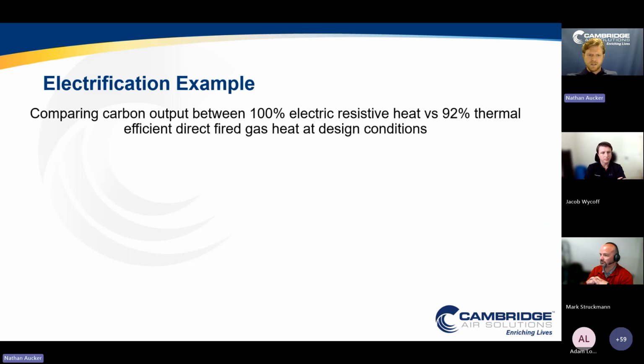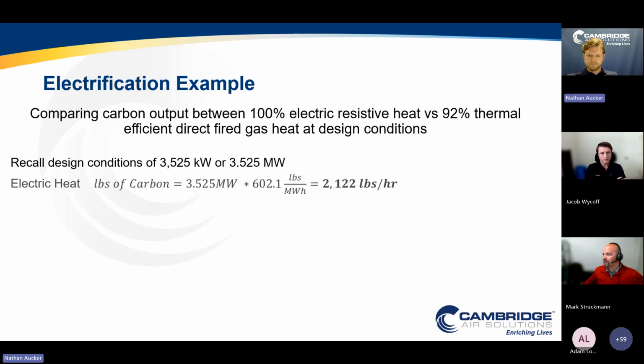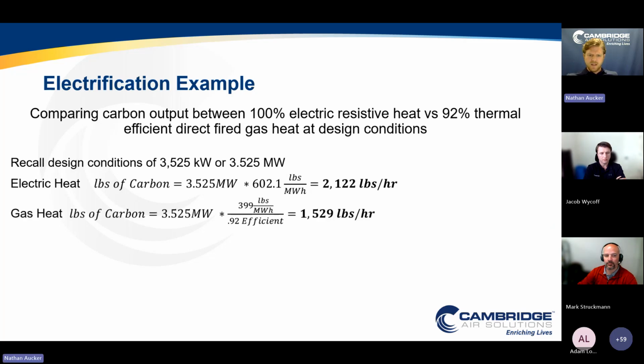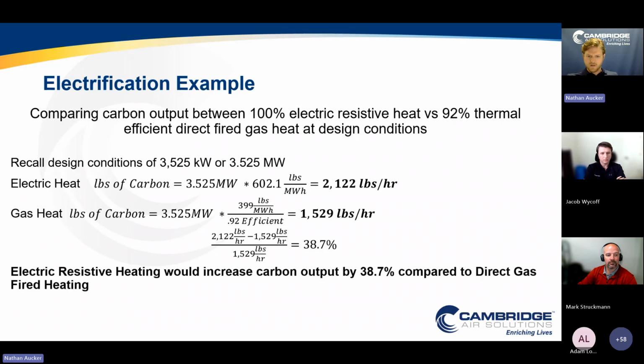Those are just inputs from the EPA. When we compare the carbon output of resistive heat versus thermally efficient direct-fired gas heat at design conditions for this example, recall the design load of 3,500 kilowatts. Applying electric heat, pounds of carbon would be around 2,100 pounds per hour. For gas heat, we're looking at 1,529 pounds per hour. That equates to a 38.7% increase when comparing electric resistive to direct-fired gas heating. So you're actually adding more carbon output by switching to electric in this case.